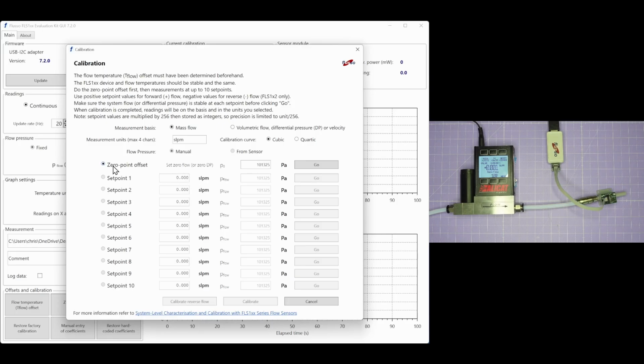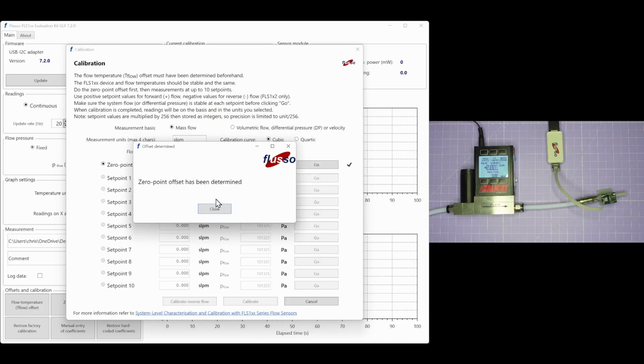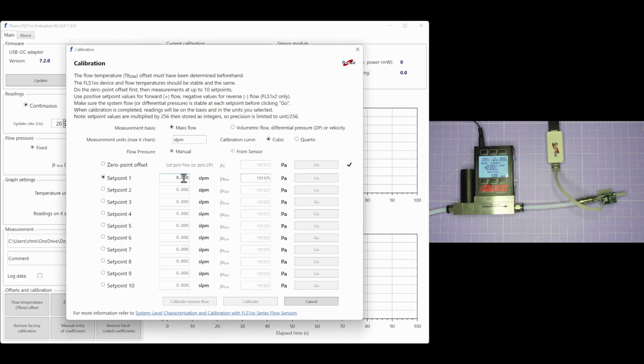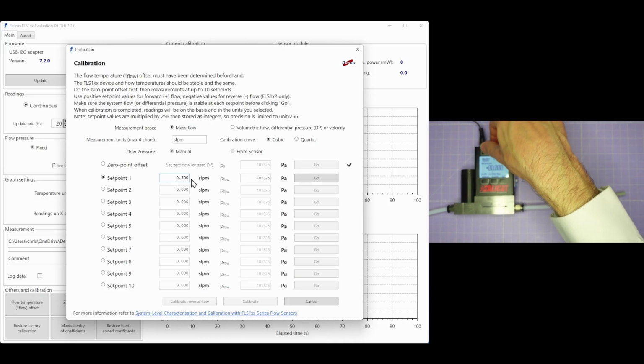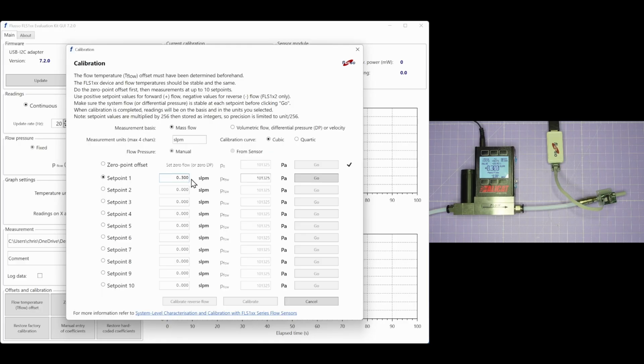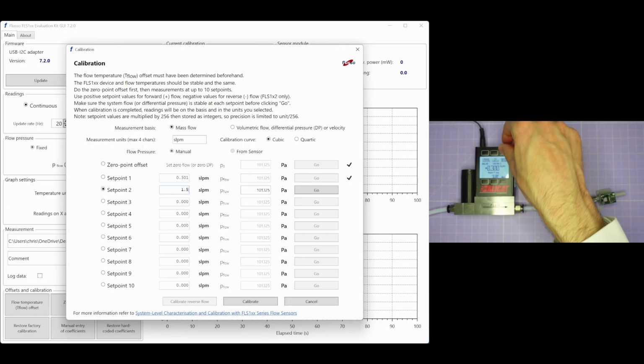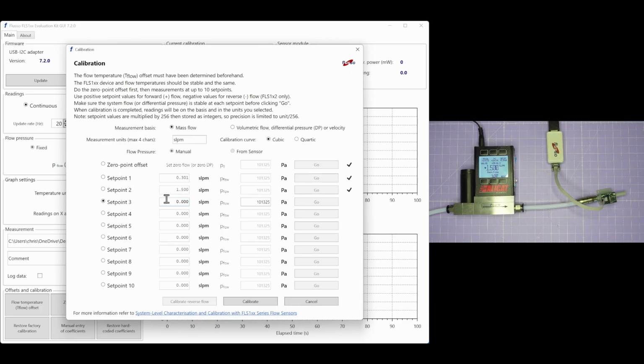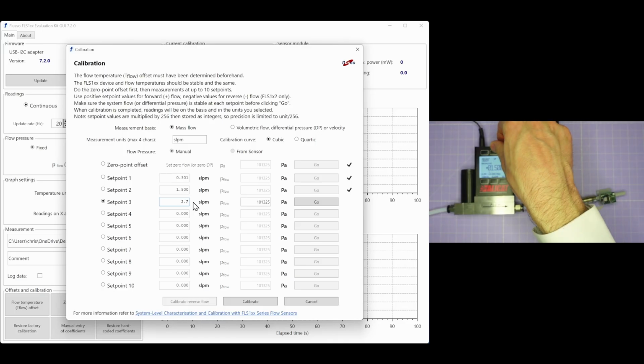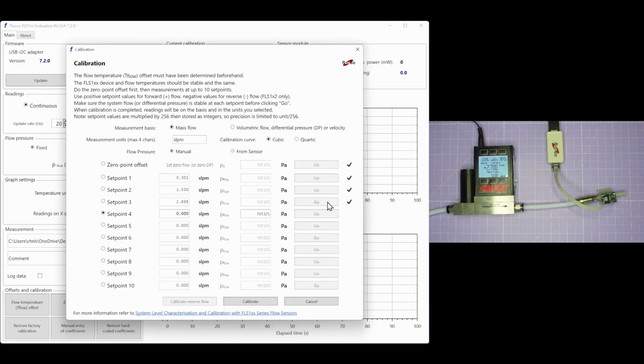So I'll start with the 0 point offset again, perform that, and then I'll enter my first set point, 0.3 litres a minute, and then I'll turn on the pump and set 0.3 litres on my flow controller. Once the flow is stabilized, I can perform the calibration. And then I'm going to repeat the set point for 1.5 litres, and 2.7 litres per minute. Once the 3 calibration set points have been entered, you can click Calibrate.